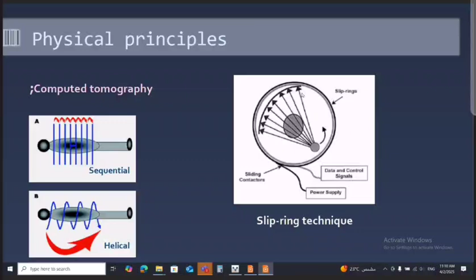The development after the helical CT was the multi-slice CT. The idea of the multi-slice CT was, instead of a single row of detectors and consequently a single image in the tube rotation, we have multiple rows of detectors, and we can acquire multiple sections in the same tube rotation. We started with 4 detectors, and the technology has now developed up to a very large number of detectors. The tube rotation was also more rapid as compared to the single row of detectors machines.